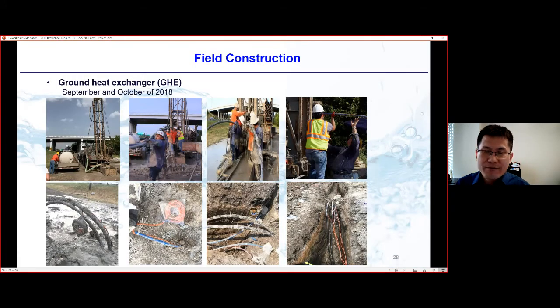These photos show the most critical component, where we get the heat from: the ground heat exchanger. Picture a vertical pipe bent in the middle. We drill a hole using this drilling machine to a depth of about 400 feet, then insert the bent HDPE plastic pipe into the hole. Inserting it is quite a challenge since it's relatively long, about 430 feet, and requires several people to insert it.